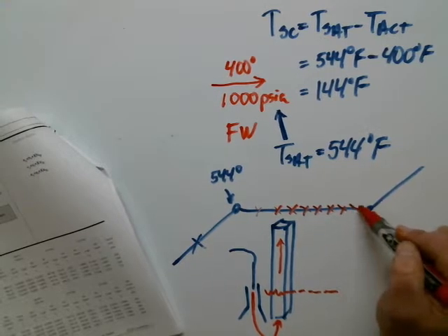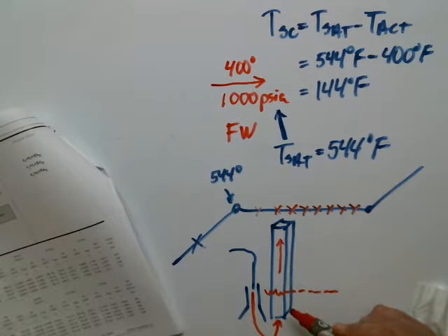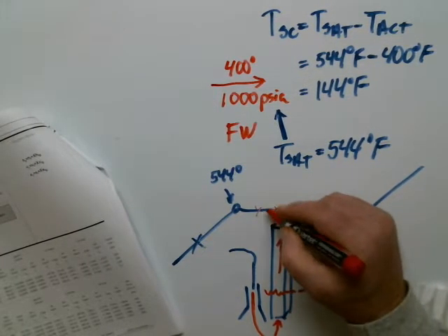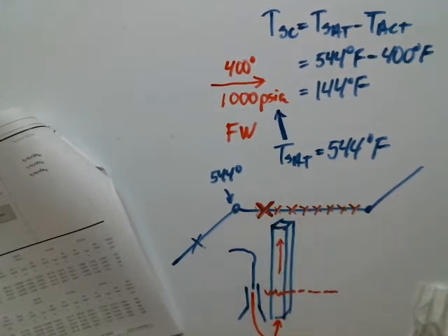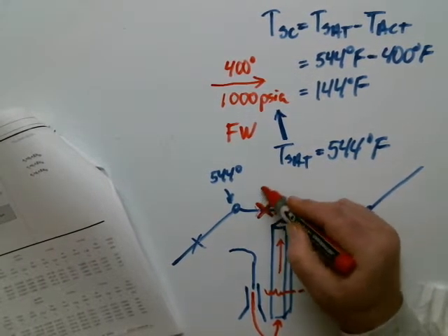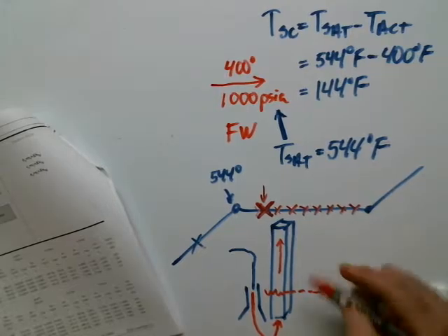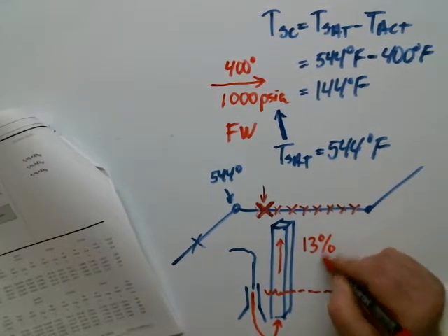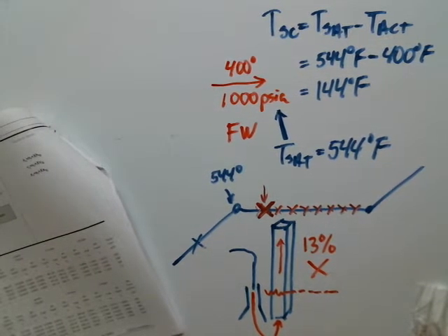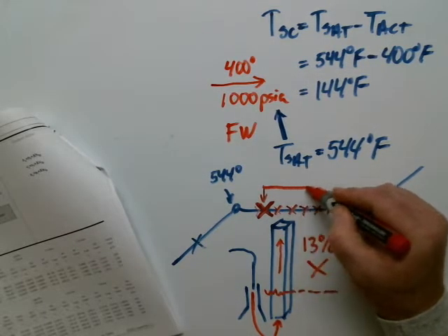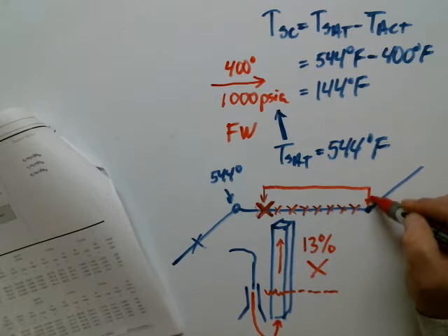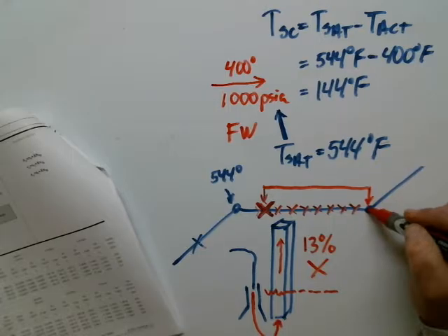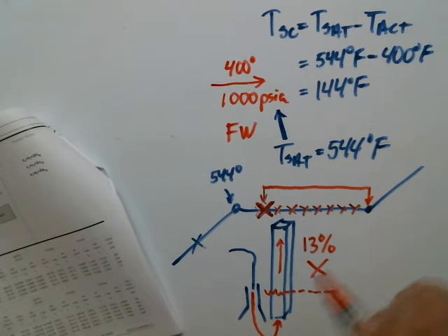The 24 heating elements essentially in series, we'll find out. And we'll find out that we exit this fuel bundle about right there on the vaporization line, which is about 13% quality. So somehow, before we ever send this steam to the turbine, I'm going to have to get it from there to there. I'm going to have to remove a bunch of moisture. And we'll figure that out too.